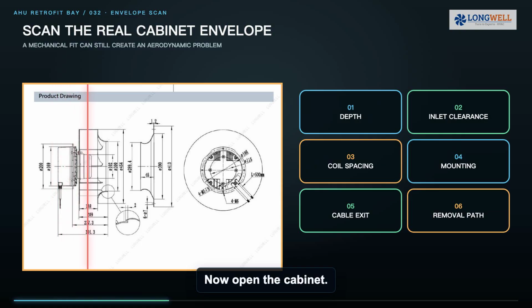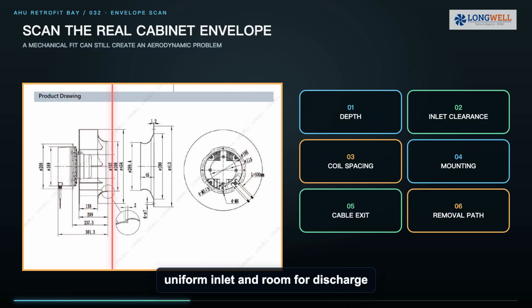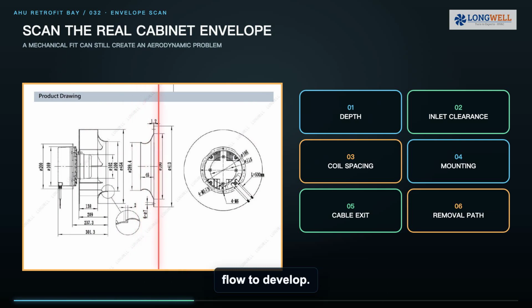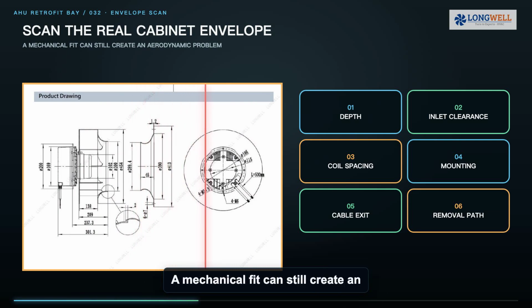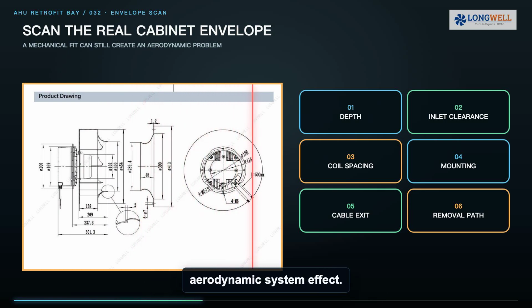Now open the cabinet. Measure depth, inlet clearance, discharge to coil spacing, mounting points, cable exits, and the removal path. A plug fan needs a clean, uniform inlet and room for discharge flow to develop. A mechanical fit can still create an aerodynamic system effect.